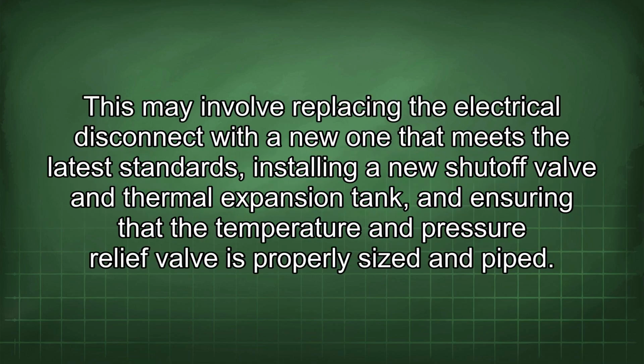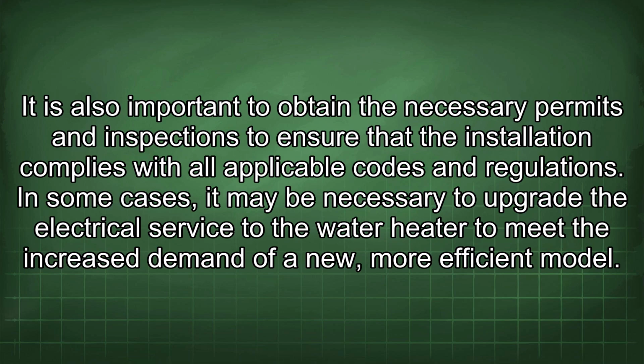This may involve replacing the electrical disconnect with a new one that meets the latest standards, installing a new shut-off valve and thermal expansion tank, and ensuring that the temperature and pressure relief valve is properly sized and piped. It is also important to obtain the necessary permits and inspections to ensure that the installation complies with all applicable codes and regulations. In some cases, it may be necessary to upgrade the electrical service to the water heater to meet the increased demand of a new, more efficient model.